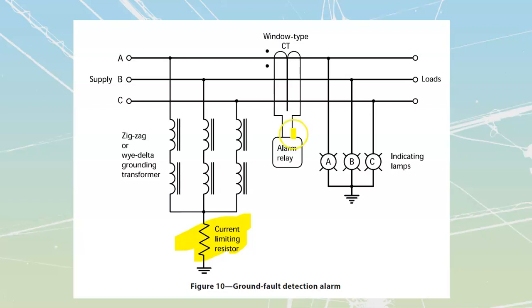The other thing we've done is taken an alarm relay and attached it with a window type of CT, one of those CTs that clamps around stuff. That window type CT is going to monitor all the lines.